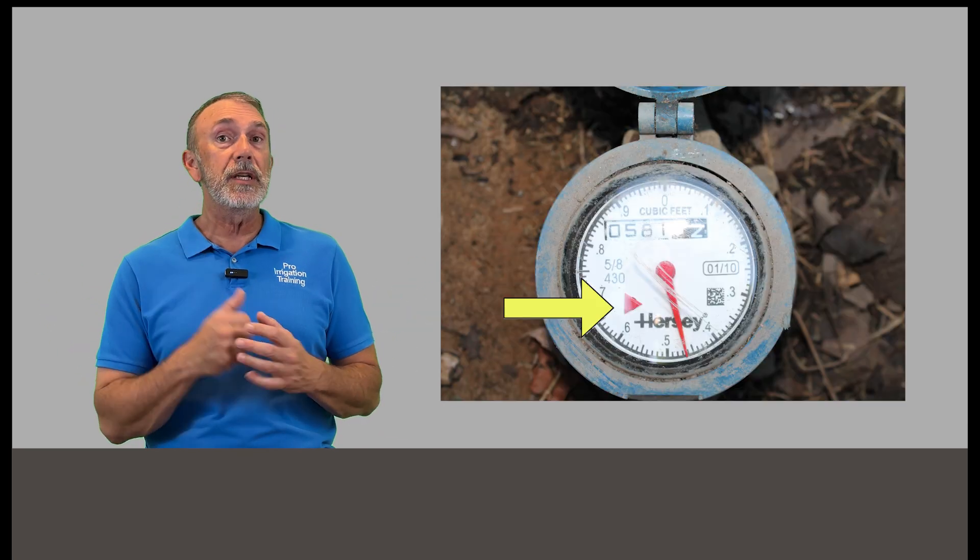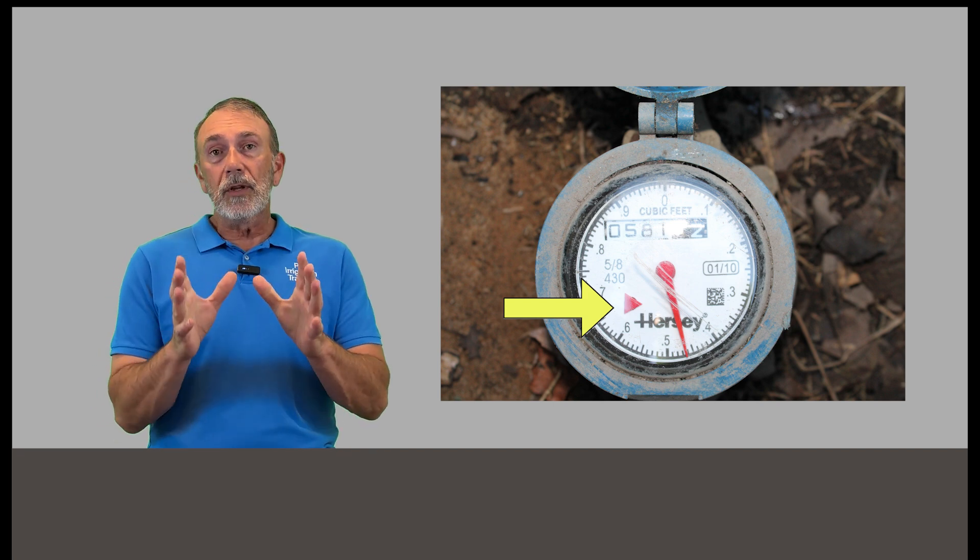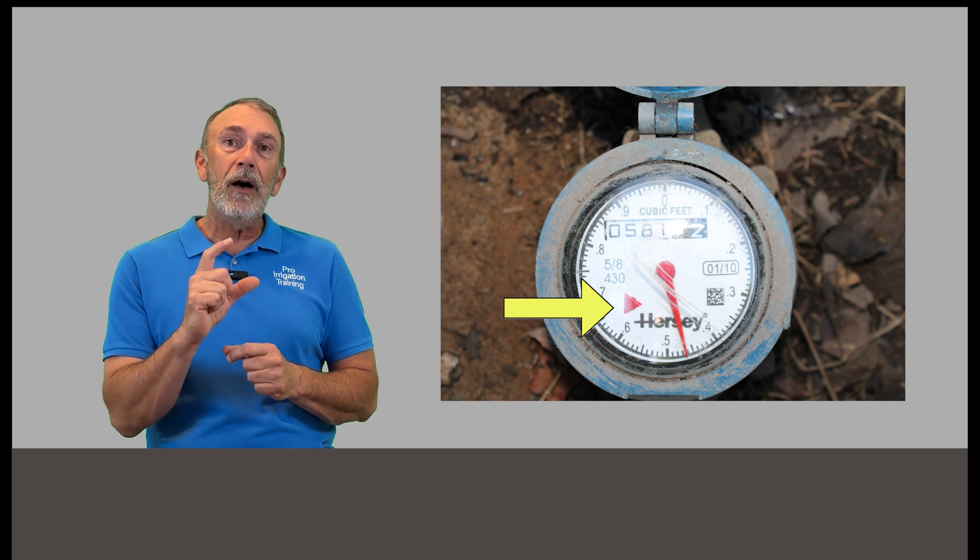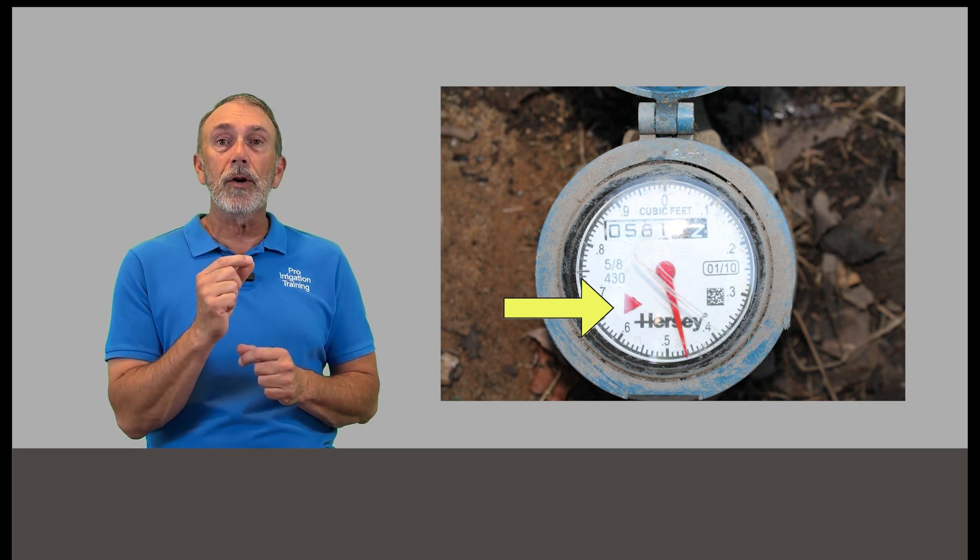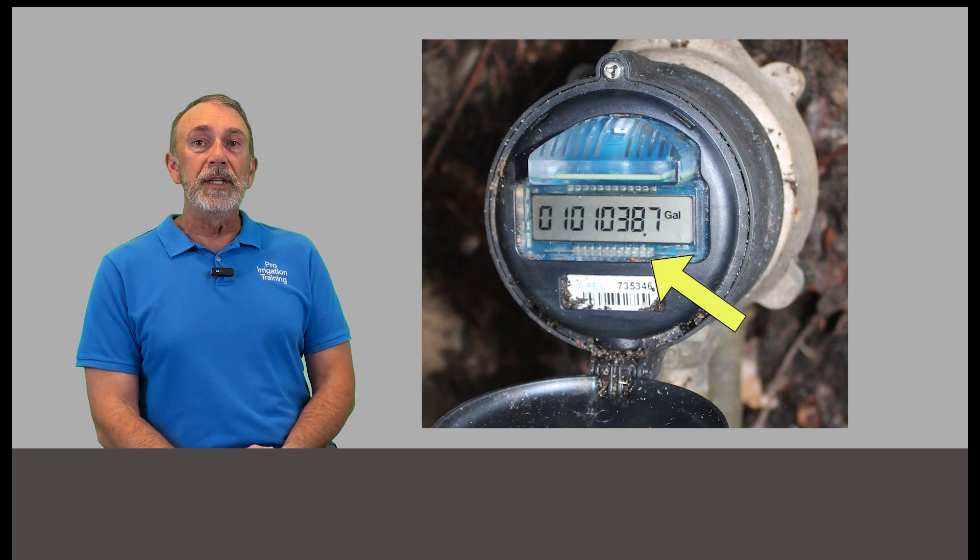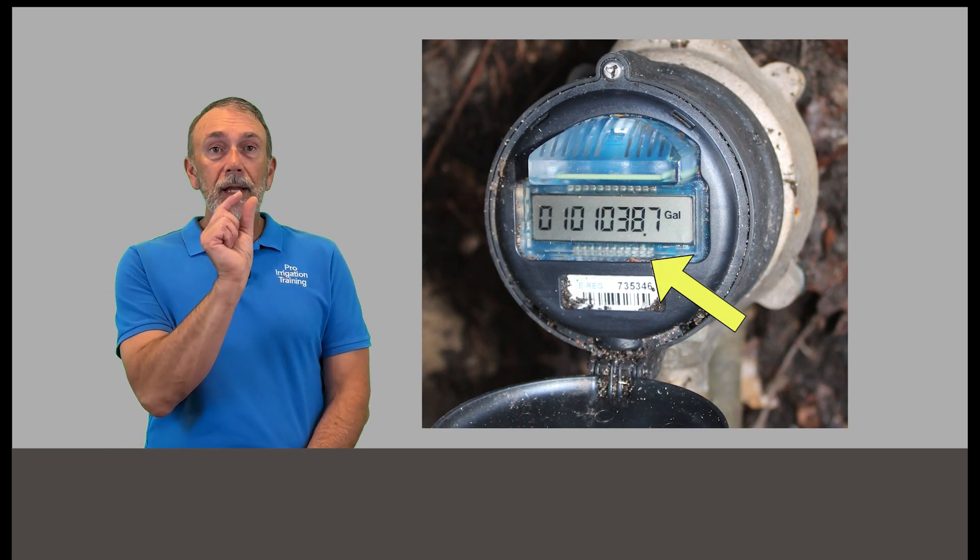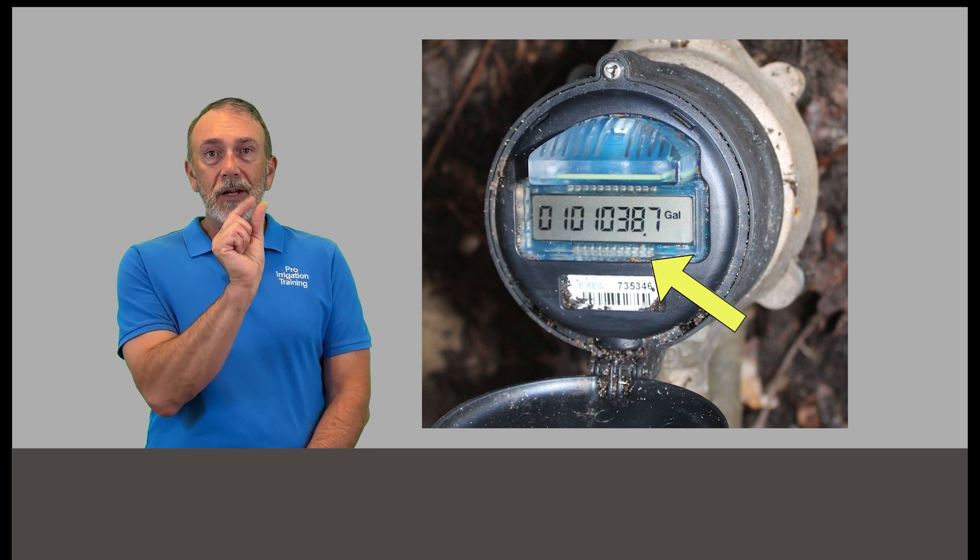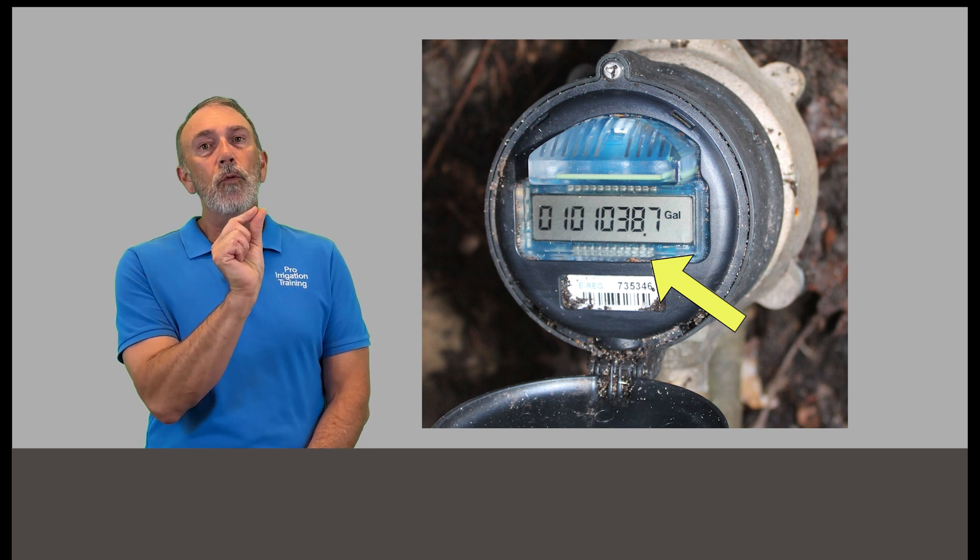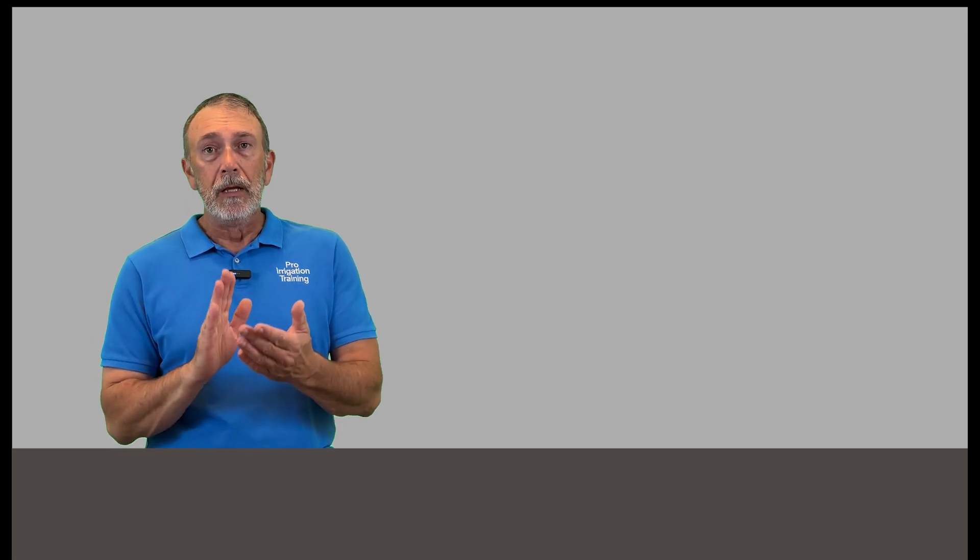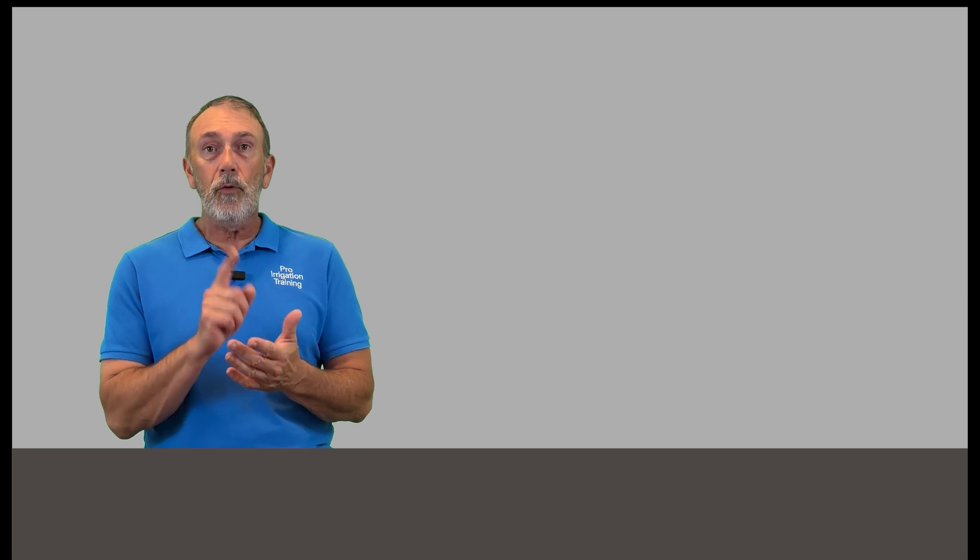If there's no wet spots, but yet the meter is turning, the leak wheel on the meter is doing a slow turn. And if you don't know what the leak wheel is, it's actually a little smaller thing on the dial that shows you small amounts of water going through. And this is for the analog meters, but on the digital meters, usually there'll be one little light or a little thing on the readout that's clicking to show that small amounts of water are moving through. And sometimes you may have to pull up the manual for that particular meter. If it's one of the newer digital meters and you can't quite figure out how to see if it's leaking, you got a phone, look up the instruction manual for that particular meter. And it'll tell you how to look for that because every meter has a way of showing small amounts, less than a gallon moving through the meter.